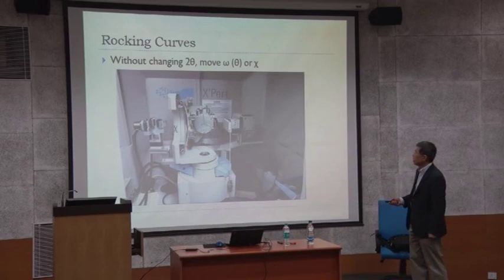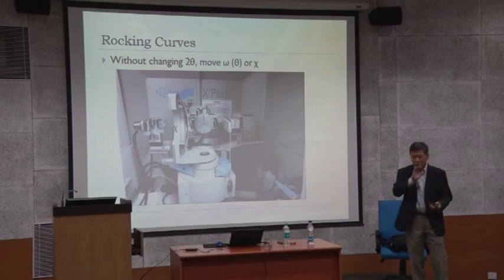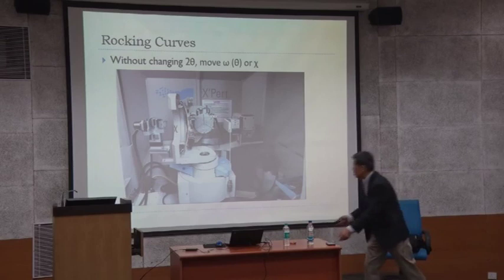We also measure other types. It's not the rocking curve — it's a different rocking. The phi angle and chi angle move this way. I talked about sample motion: theta motion is this, chi motion is this, and phi motion is that way. So that's four different angles, and it is an actual four-circle diffractometer. It's similar to a single crystal machine, which has a very similar type of motors, and they attach a CCD camera to capture all the diffraction peaks.